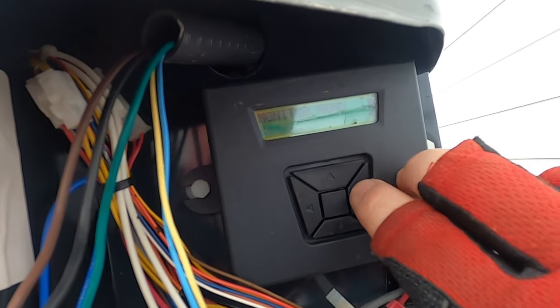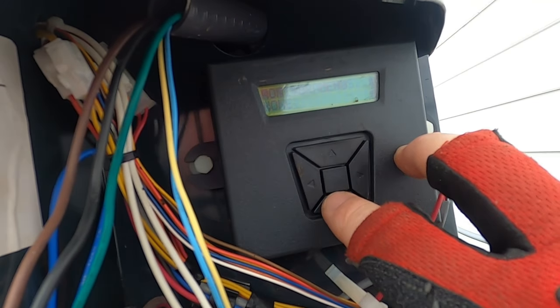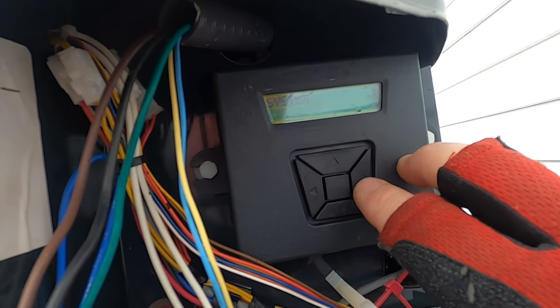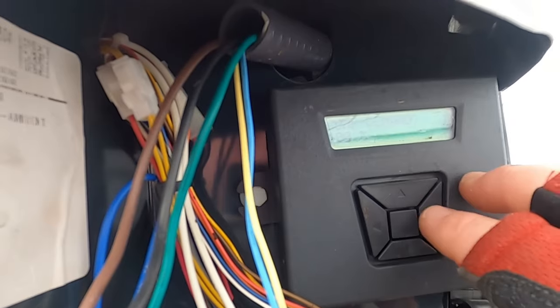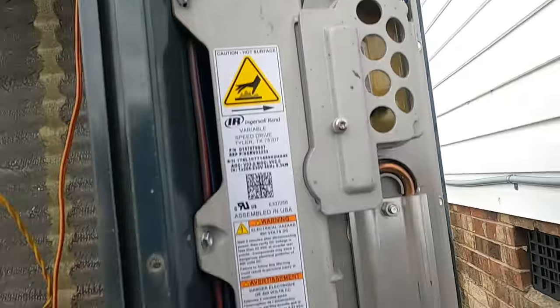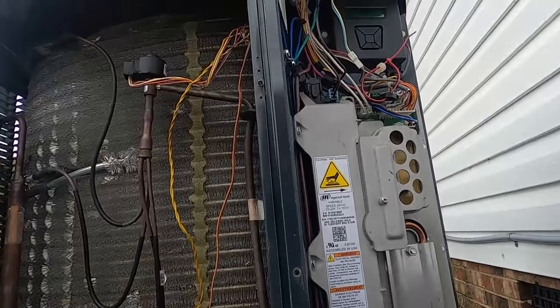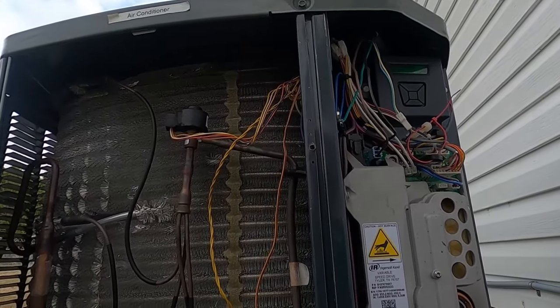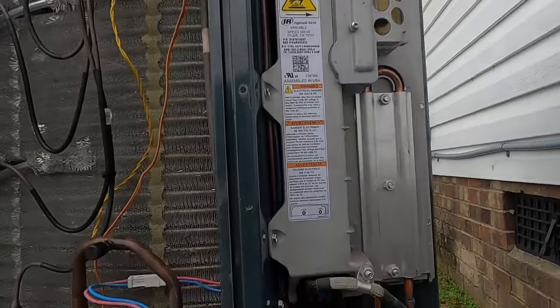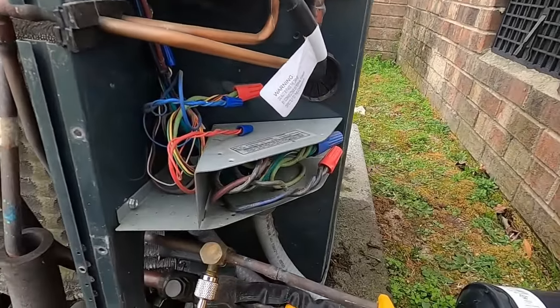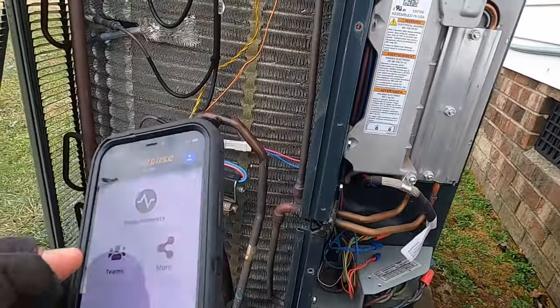Go in here, monitor menu, go down to system, go over one. So we are running at a 100% demand. I don't know how well you see that, but we're running at 100%. That's what I wanted to check. It was 75. I turned it down to 62 just to get it to ramp all the way up. And let's see what our pressures are real quick.